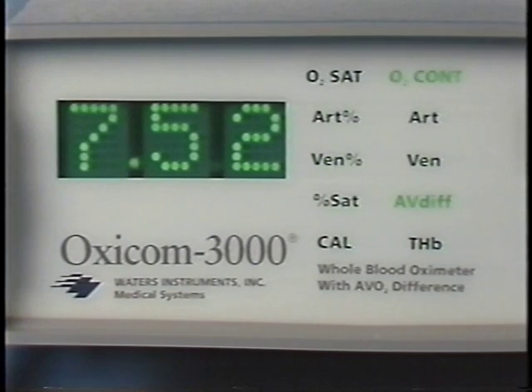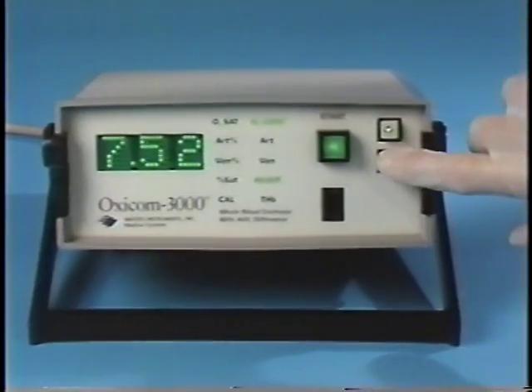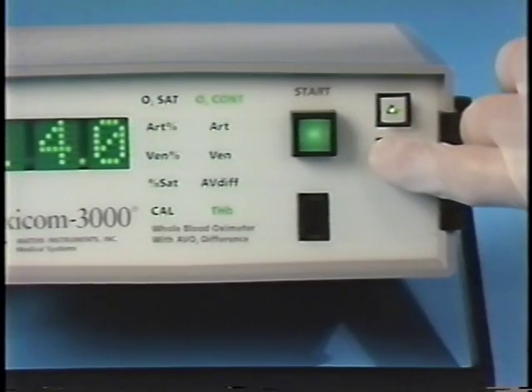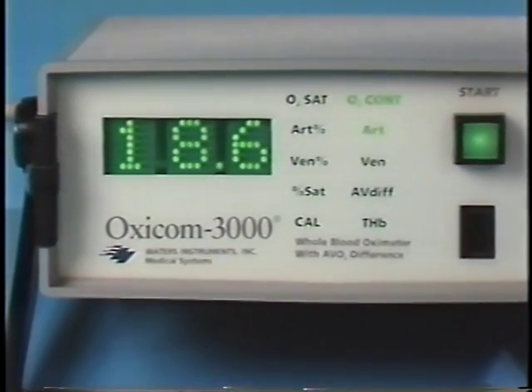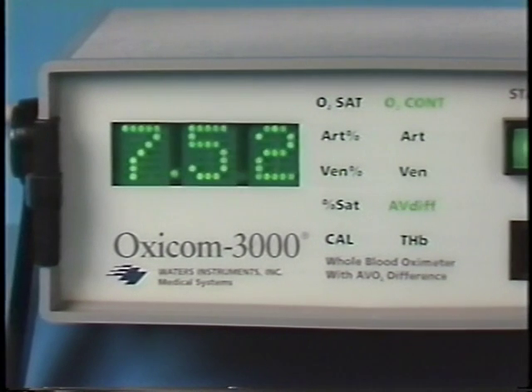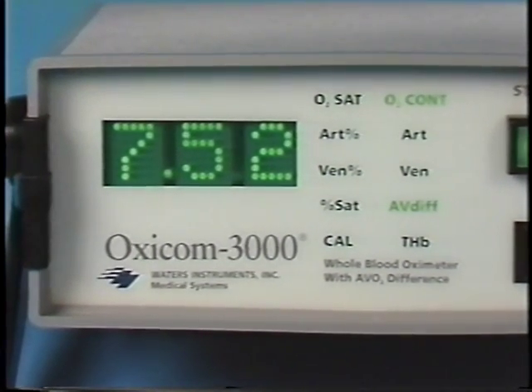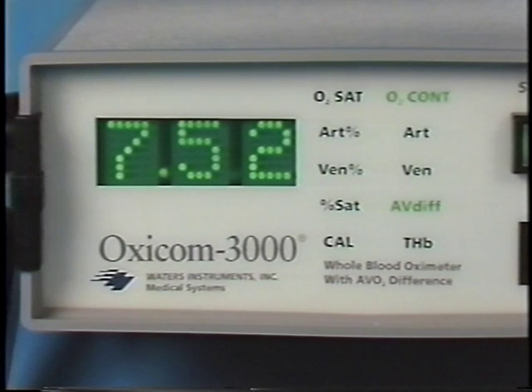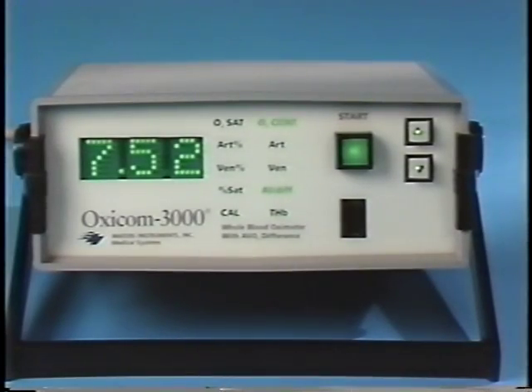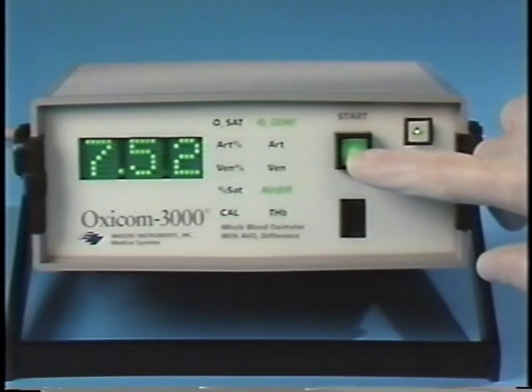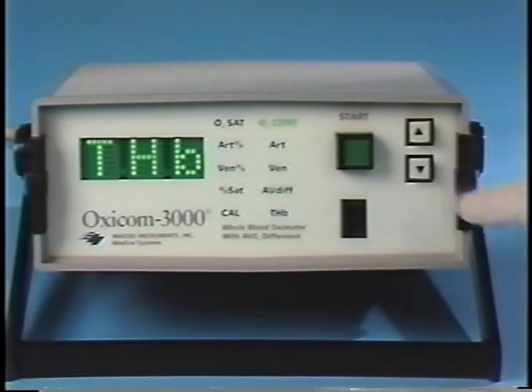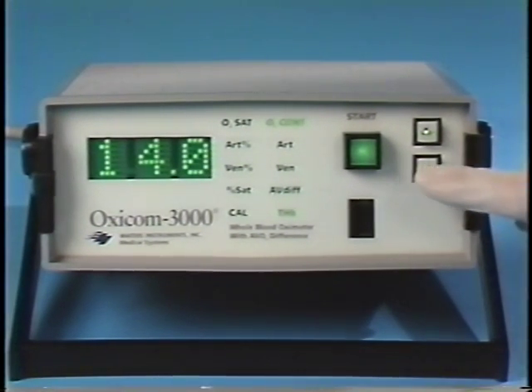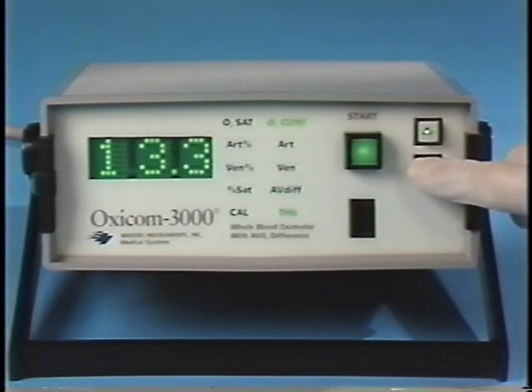To review each value, just press either of the green arrows. THB, arterial percent, arterial content, venous percent, venous content, and AVO2 difference. The Oxicom 3000 will cycle through each value for your verification. To perform a second oxygen content and AVO2 difference, press the green Start button. THB will again be displayed. If a new patient is studied and the total hemoglobin is different than the previous value, make the necessary change and proceed with the two new samples.